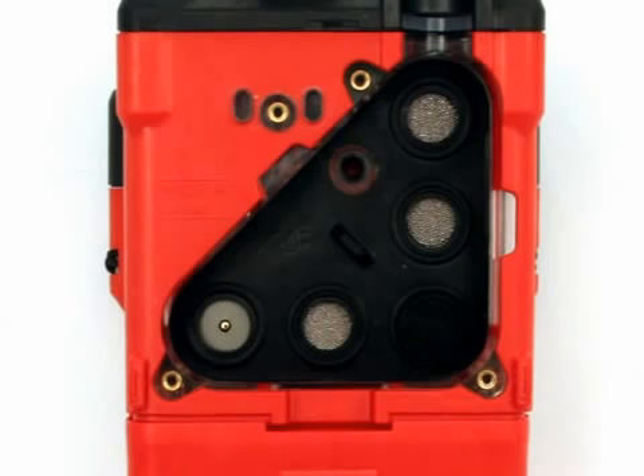The CO sensor will respond if exposed to hydrogen sulfide and certain hydrocarbon gases. The charcoal filter scrubs these gases out of the gas sampled to avoid false CO readings. The H2S absorbing material added to the charcoal filter extends its H2S absorbing life. If false CO readings are noticed, especially high readings in the presence of H2S, change the charcoal filter disc.